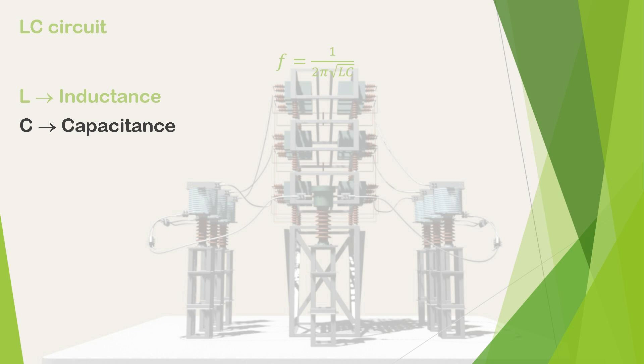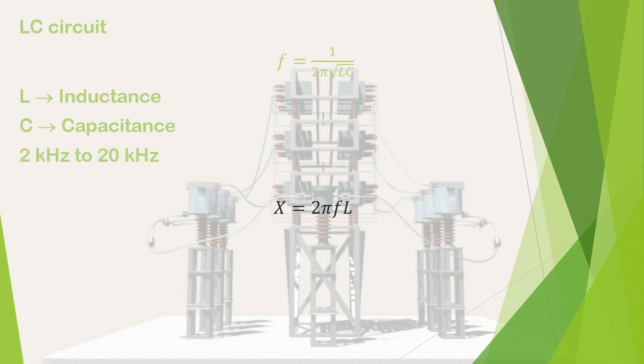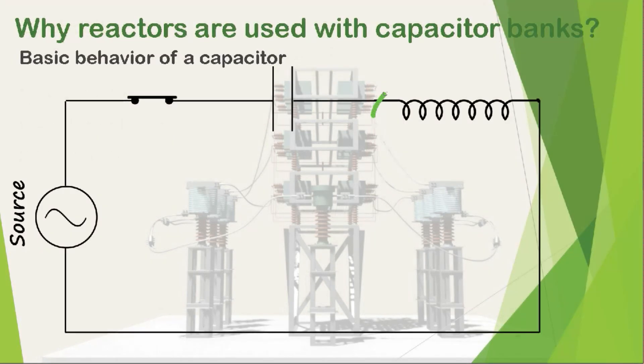Because of this resonance circuit, the initial charging current will oscillate with a very high natural frequency, which may be somewhere between 2 kHz and 20 kHz. We know that inductive reactance X equals 2πFL, where F is the frequency of the current passing through the inductor and L is its inductance. Even if we connect an inductor of very low value, because of the high frequency, this inductor can offer a very high reactance to the circuit, which opposes the current flowing through the capacitor — and in this way, we can limit the inrush current of the capacitor bank.